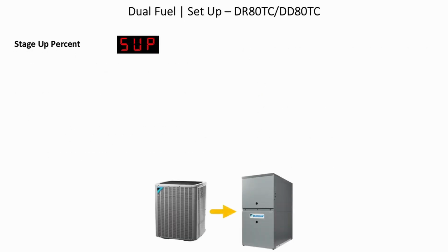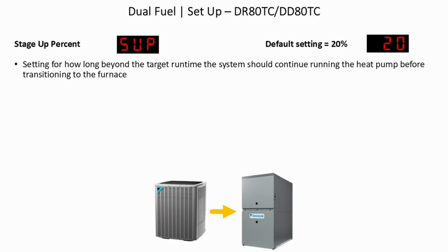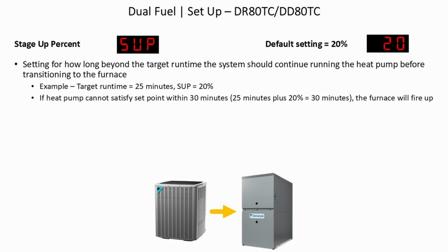Stage up percent shows on the display as SUP, default setting 20%. This is the setting for how long beyond the target runtime the system should continue running the heat pump before changing over to furnace. For example, the target runtime is 25 minutes. The SUP is 20%. If the heat pump cannot satisfy the set point within 30 minutes, 25 minutes plus 20%, which is 30 minutes, the furnace will fire up.